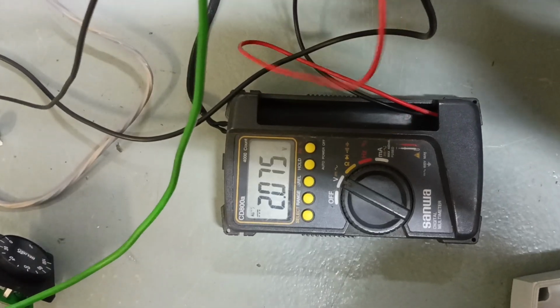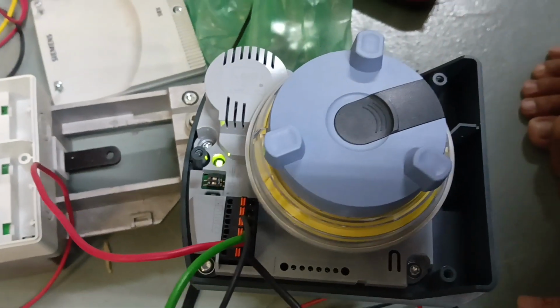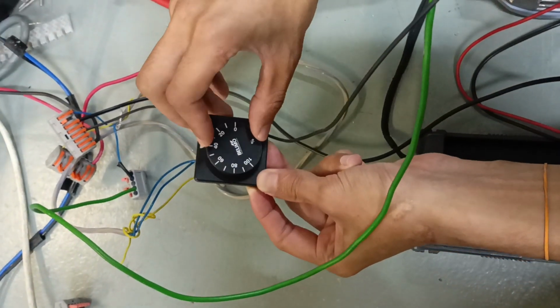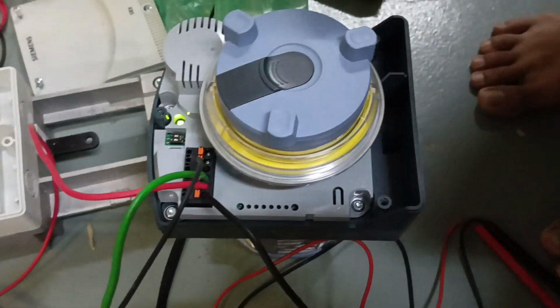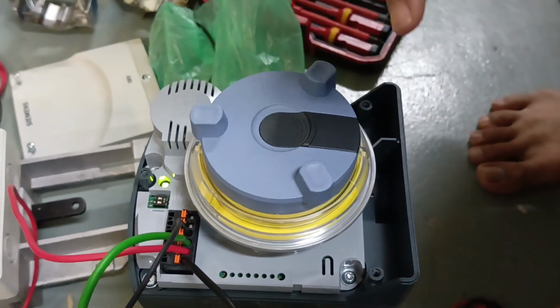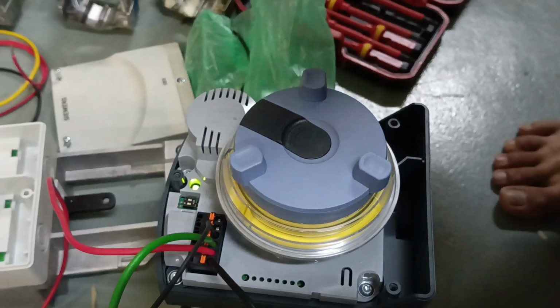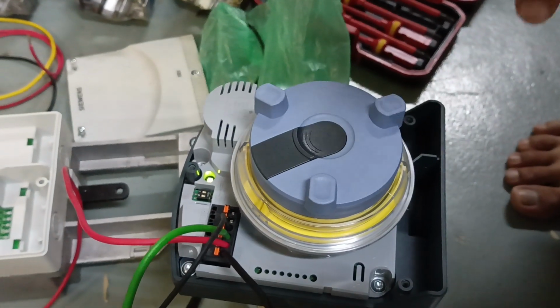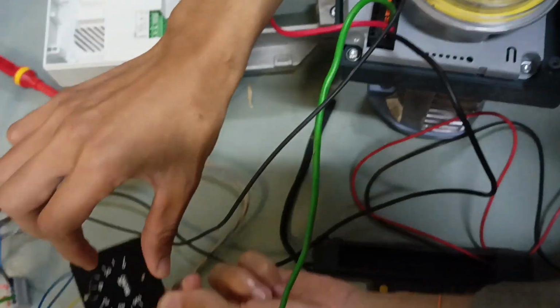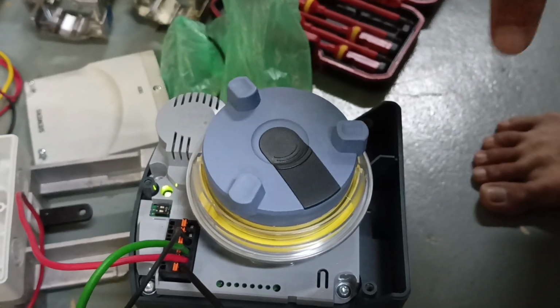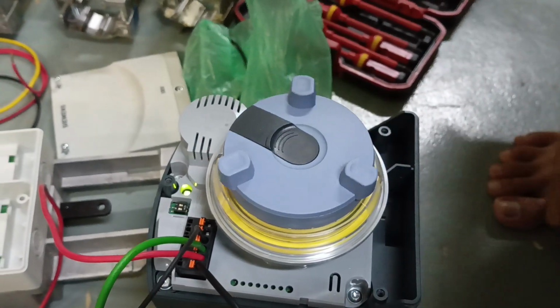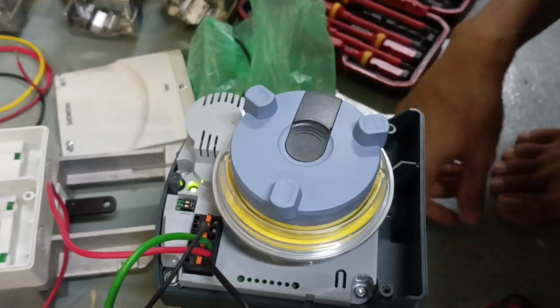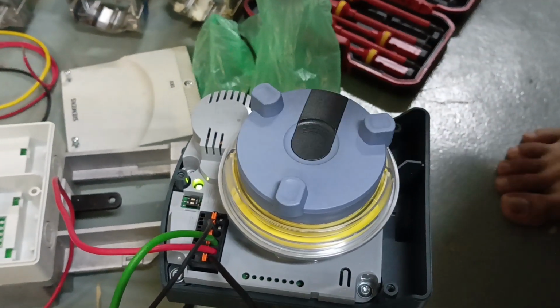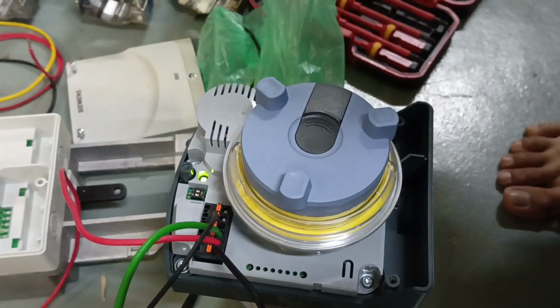DC. So we got signal and feedback. When I change, for example, to 5 volt, the actuator will rotate clockwise or anti-clockwise to open, and then the other way to close. For example, anti-clockwise is close, clockwise is open. So that's how we check whether the actuator is okay or not.